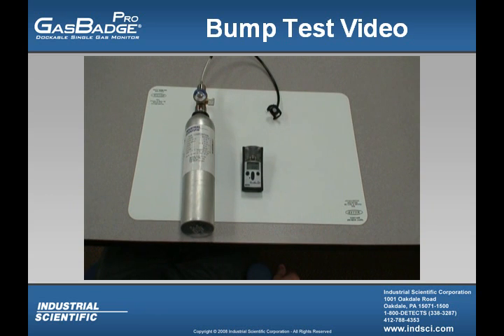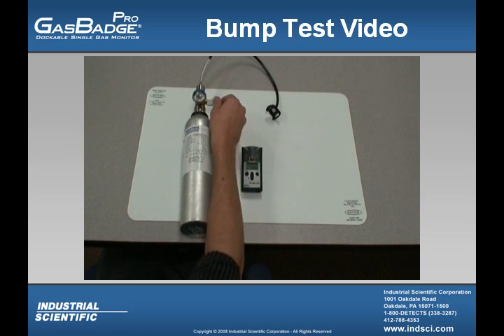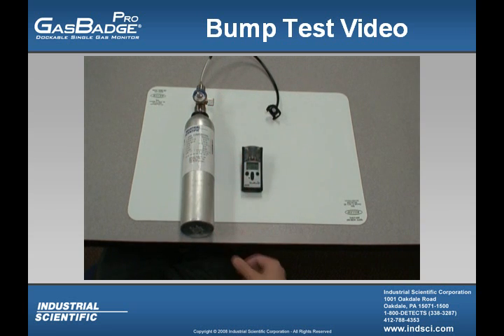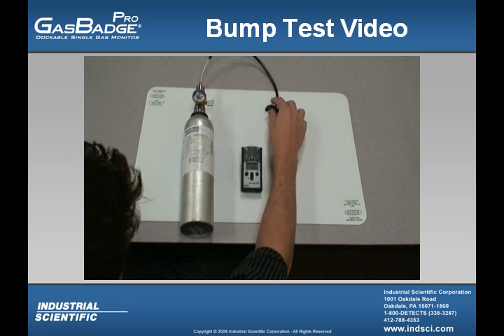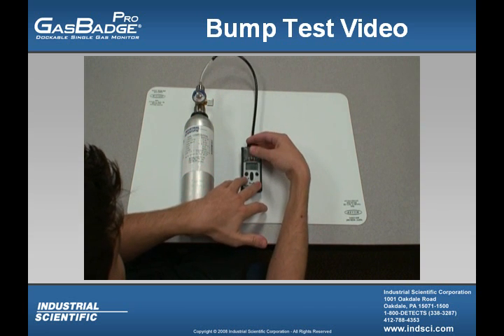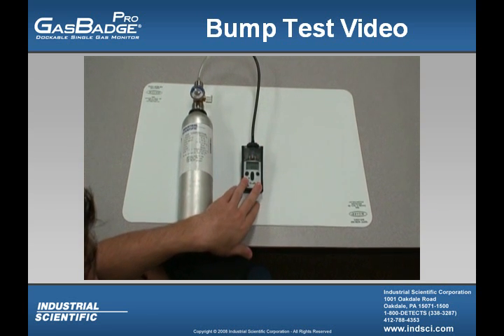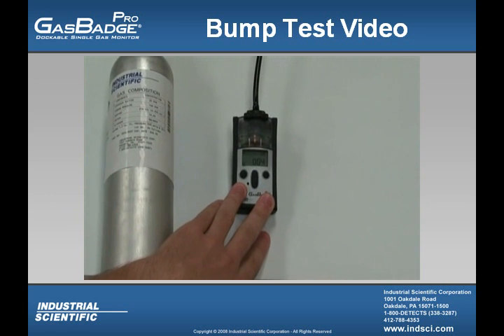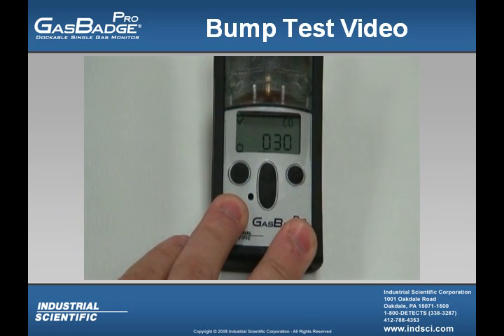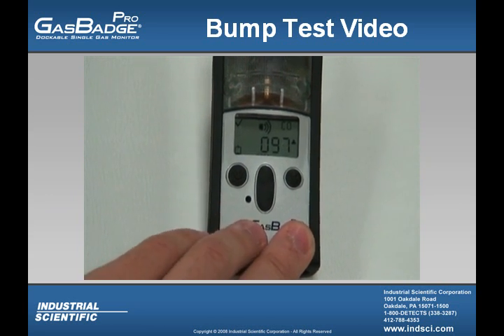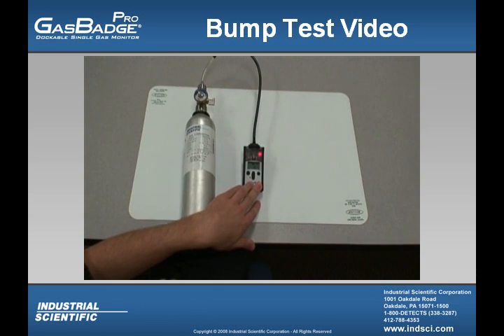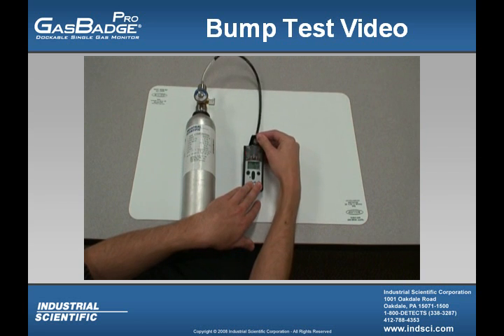If the bump test feature in the GasBadge Pro is disabled, there is still one other way to perform a bump test, and that's the manual version. What you want to make sure is that you're in the real-time operation screen. Then from there, you're going to want to open up the calibration gas bottle's regulator, apply your cal cup, and make sure that the sensor's display increases. You're going to want to check for a low alarm and high alarm. Once the user's satisfied, they can remove the cal cup, turn off the bottle of gas, let the GasBadge Pro's readings decrease, and the bump test is finished.